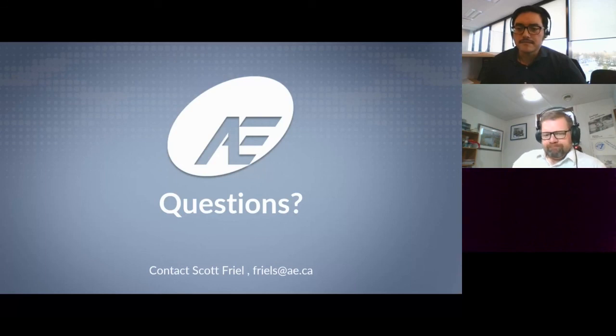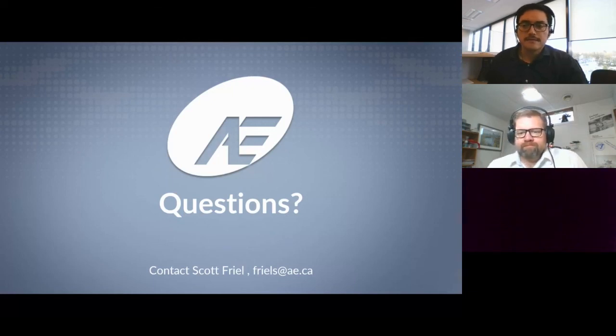Thank you, Scott. We have another comment from Chris Brado: instrumentation and controller replacement schedule depends widely on the item and service. Jared followed up with: computers 5 years, HMIs 10 years, PLCs 15 years, and he recommends instruments be replaced along with the PLC at 15 years. Not a lot of people do that, but people seem more concerned about keeping operation and maintenance costs low, because it's a pretty big bill to go in and replace instruments, even though it's a good idea.